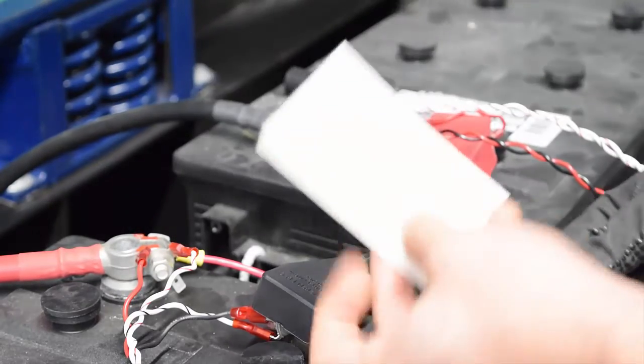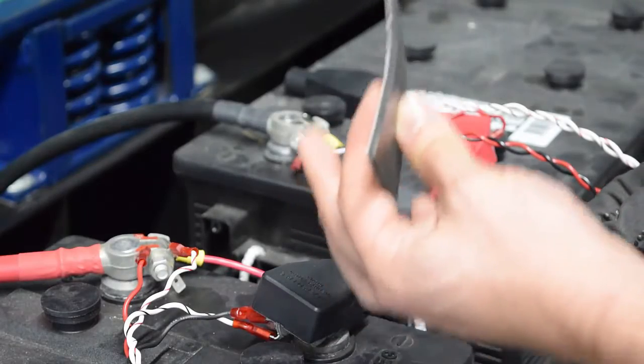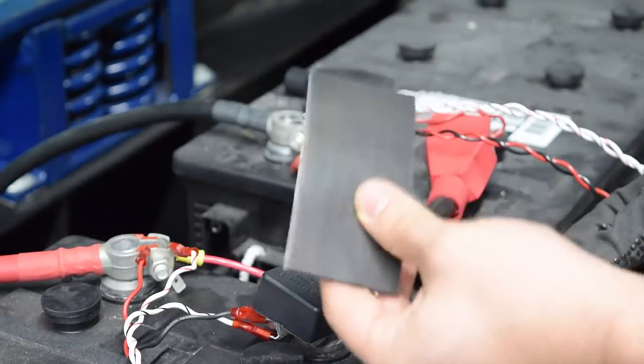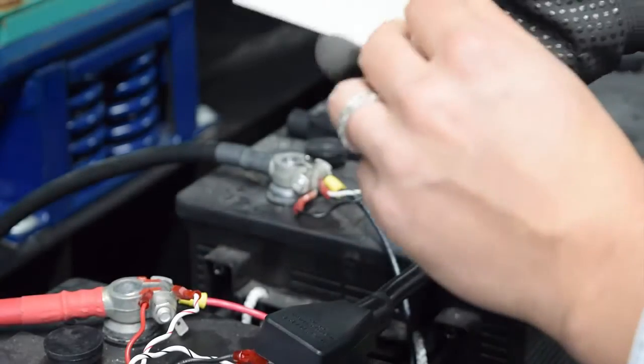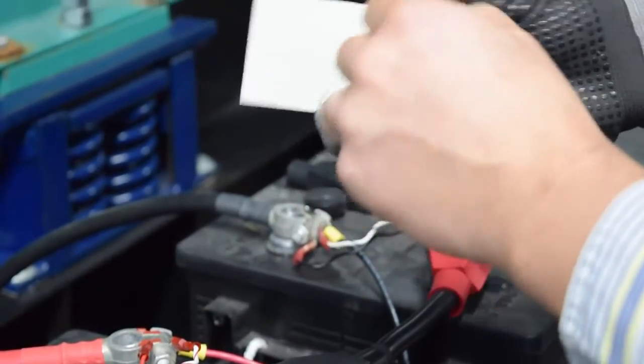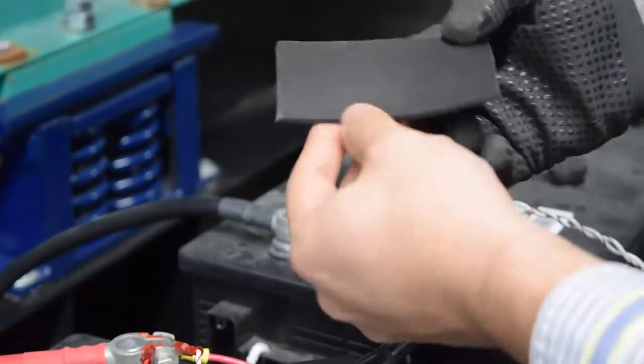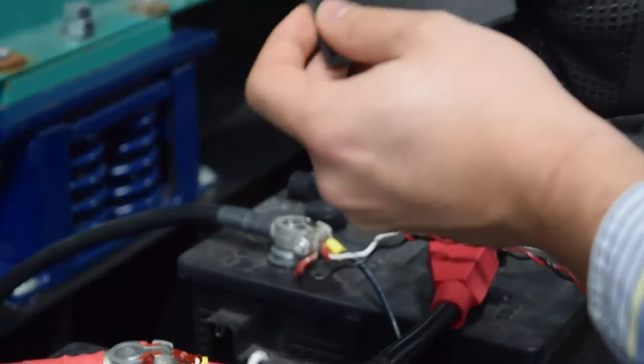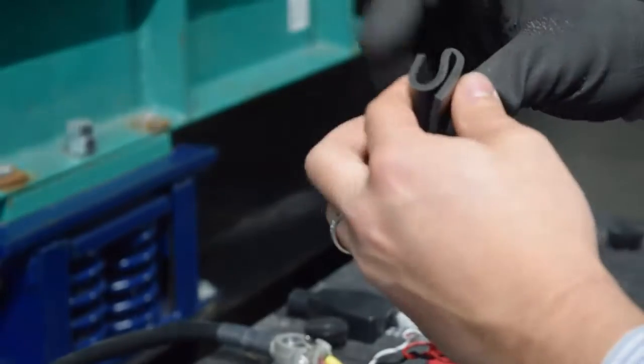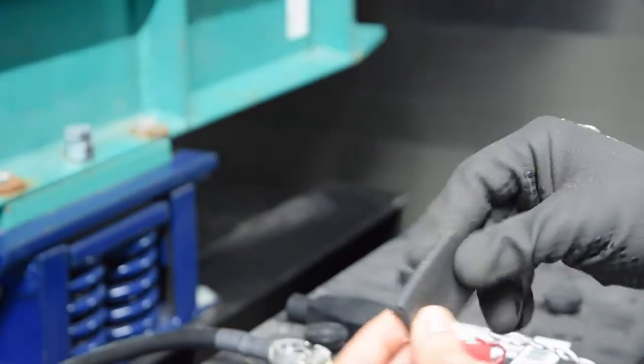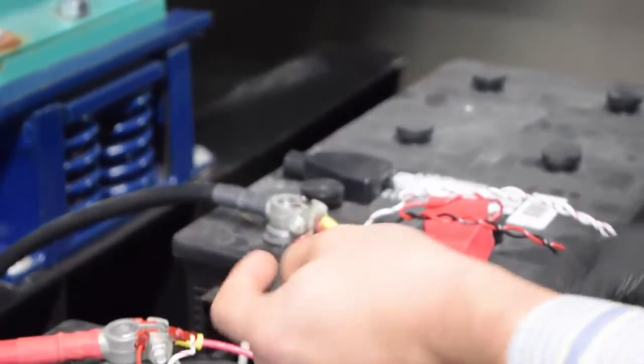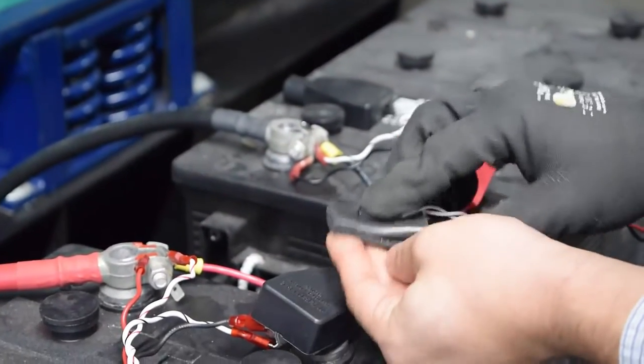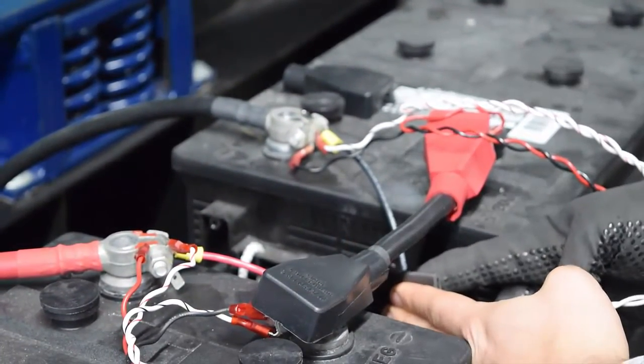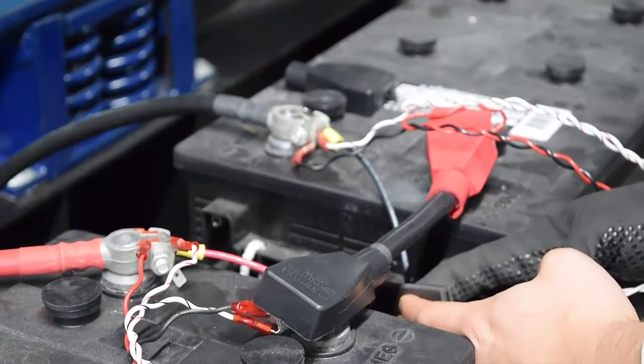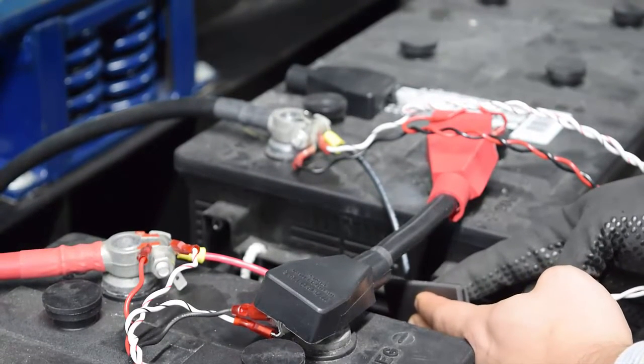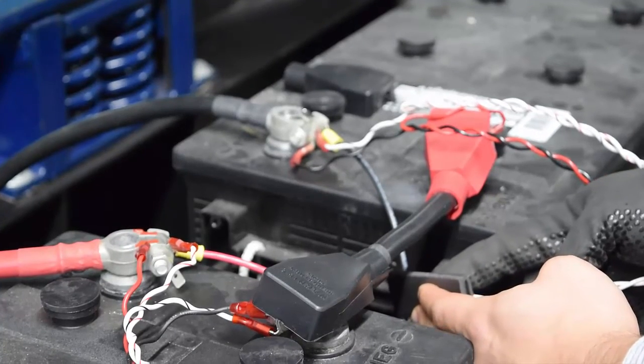And we provide a self-adhesive foam pad included for mounting the temperature sensors to the battery. What you do is peel the cover from the foam pad, revealing the sticky tape, and then fold it to a Z fold, kind of like this, and place the sensor onto the side, and the sticky side, and shove it between the two cells. Now this should provide enough compression between the batteries to keep the temperature sensor in place.